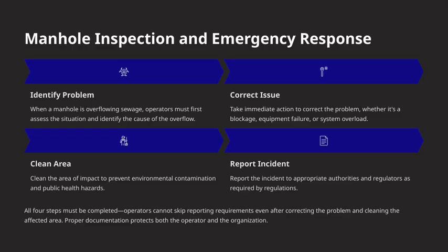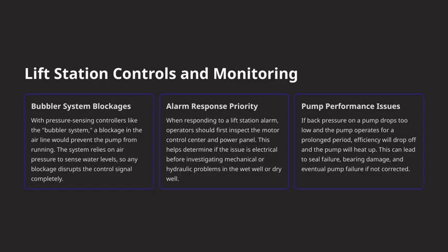these emergency situations effectively. Let's take a closer look at lift station controls and monitoring, starting with bubbler system blockages. When we use pressure-sensing controllers, like the bubbler system, the system depends on air pressure to monitor water levels. If there's a blockage in the air line, it prevents the pump from running because the system can't detect the water level properly. It's important to remember that any disruption in the air pressure signal can cause the system to malfunction, so regular checks are key.